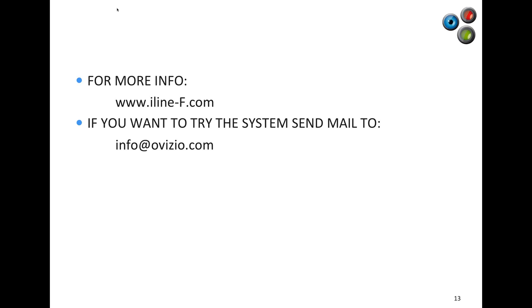So we have patented a method, and the basic principle, so with holography we have the capability to refocus objects that are within the hologram, and a hologram is typically a cube with sides of about half a millimeter. So in fact what we do when we measure viability, first of all, you will see that healthy cells, when they have an intact membrane, will behave like a lens, and they will create an out of focus light spot, so a very tiny spot, where a dead cell that has a porous membrane and is losing its cytoplasm will diffuse light.